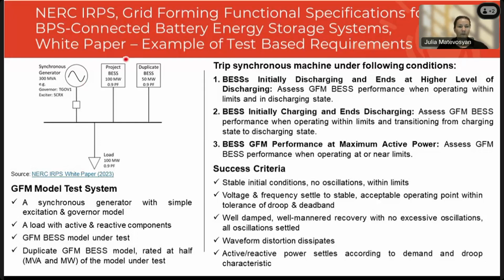In the test setup, the device under test is, for example, this 100 megawatt BESS. There is another same model connected that's half the size, a synchronous generator and the load. And the load is dimensioned such that under disconnection of the synchronous generator, these batteries are sufficient to support this load. So there is nothing strenuous from an energy or capacity perspective, and it's more to test grid forming capabilities in the subtransient and transient time frame. The reason why there are these two batteries is first to make sure that there is no control interaction between two grid forming resources connected at the same POI, and also that there is proper power sharing happening once the synchronous generator is disconnected, and droop response is working as intended.